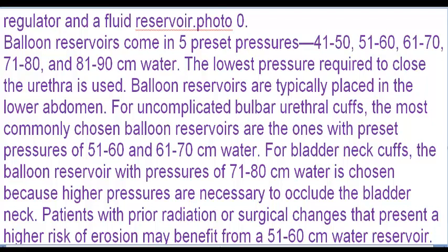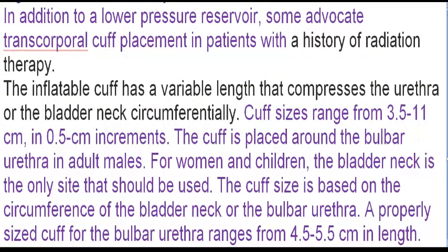For uncomplicated bulbar urethral cuffs, the most commonly chosen balloon reservoirs are the ones with preset pressures of 51-60 and 61-70 cm water. For bladder neck cuffs, the balloon reservoir with pressures of 71-80 cm water is chosen because higher pressures are necessary to occlude the bladder neck. Patients with prior radiation or surgical changes that present a higher risk of erosion may benefit from a 51-60 cm water reservoir. In addition to a lower pressure reservoir, some advocate transcorporal cuff placement in patients with a history of radiation therapy. The inflatable cuff has a variable length that compresses the urethra or the bladder neck circumferentially.